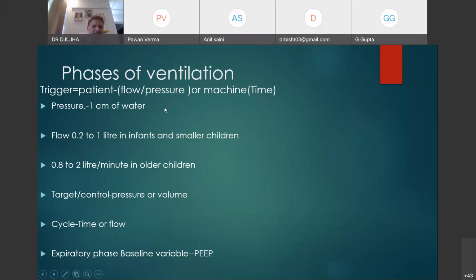So what is this? If you set pressure trigger on the ventilator, it means whenever the pressure in the respiratory airway becomes -1 centimeter, when the patient starts to take a breath. I have already said spontaneous breathing is a negative pressure ventilation. So in any child, pressure trigger is set at this -1 centimeter, and if the pressure becomes this, the child starts to take a breath, and the machine will sense this pressure and deliver the breath. The other is the flow trigger. We set the flow trigger according to the age of the child, but roughly it is 0.2 to 1 liter in infants, 0.8 to 2 liter in older children. And as the flow inside the airway becomes this, the machine will sense this flow and deliver the breath. So this is the trigger.